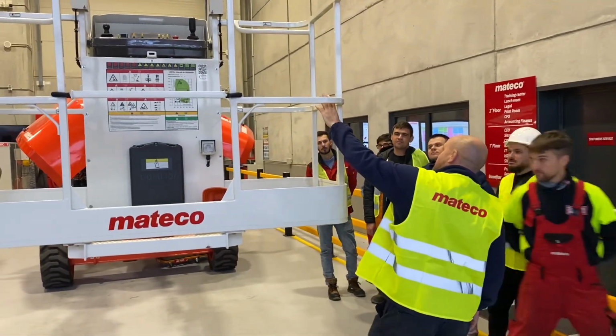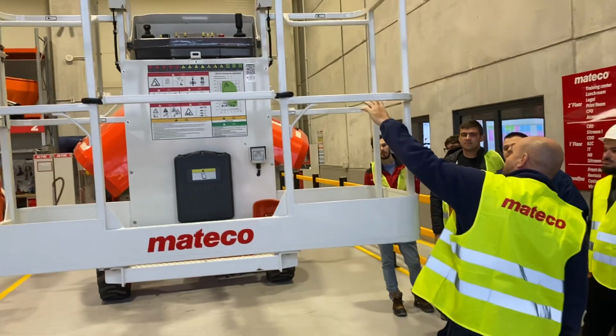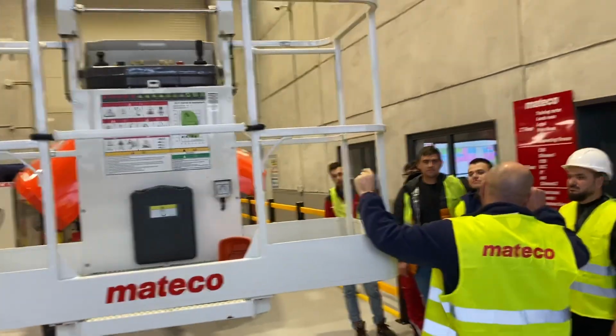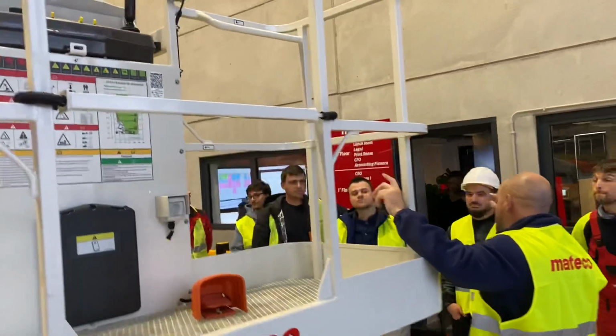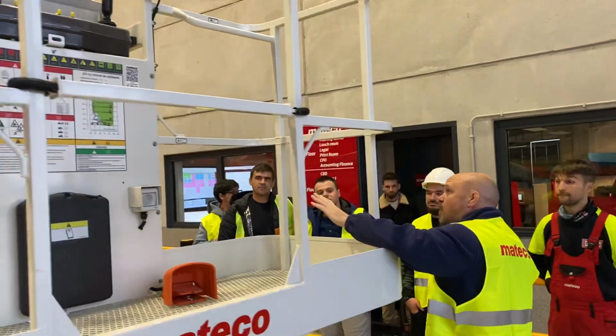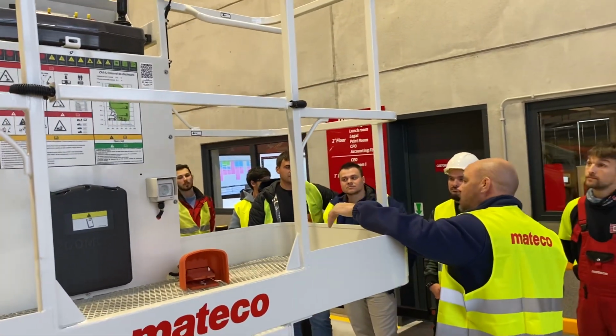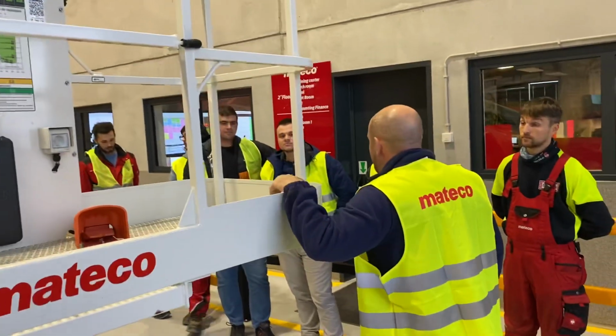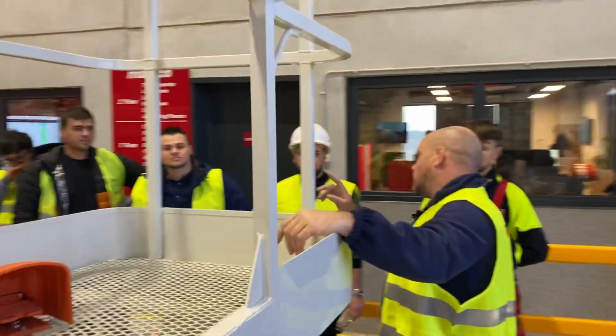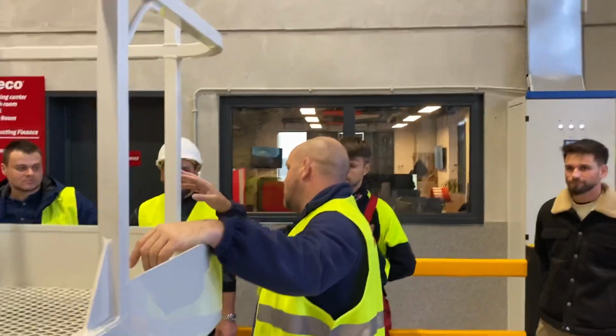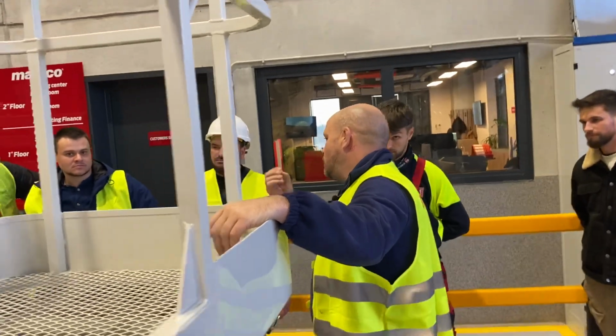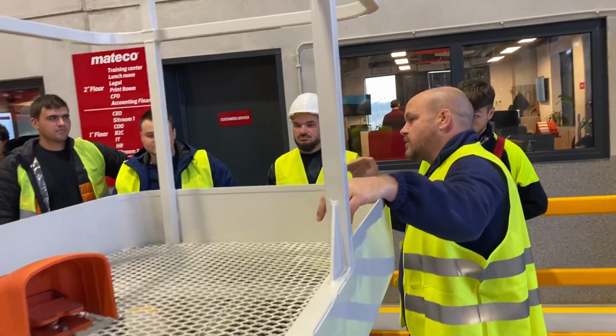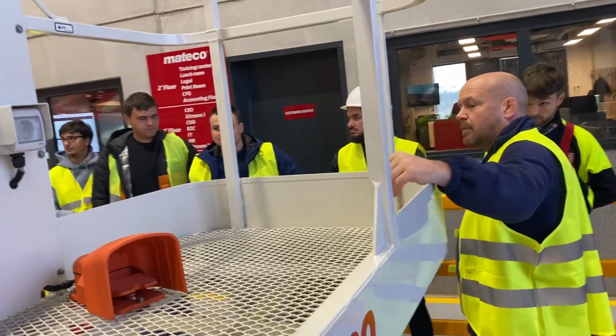The anti-entrapment system on this is just a solid steel bar, and inside we have a Telemecanique switch either side that if you push it forward, it's pressed, it stops the function. To reset it, just take your foot off the pedal and put it back on. It will leave it as a fault description on the fault history, but it won't stay there as an alarm, it's just there as evidence that it happened, okay?